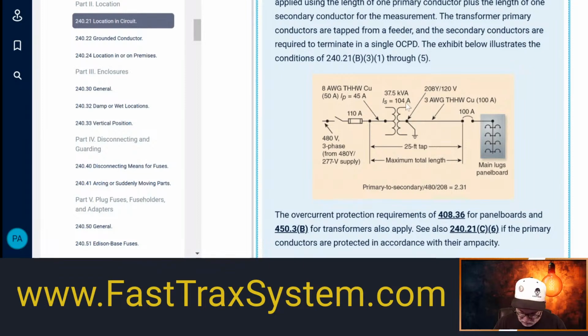So the secondary amps would be 37,500, and we're going to divide that by, what did we say it was? 360.256, which is the 208 times the square root of 3. Remember that? So we divide that. 37,500 divided by 360.256, and that is 104. So that's where they get this right here.